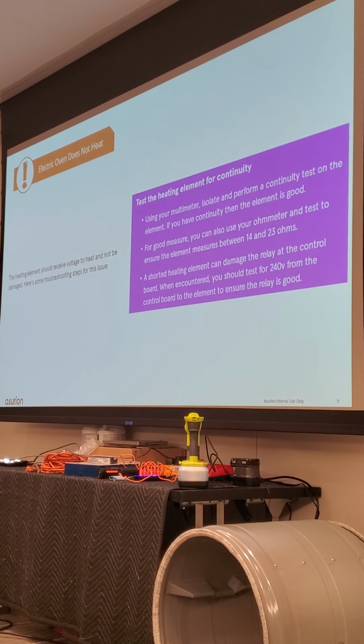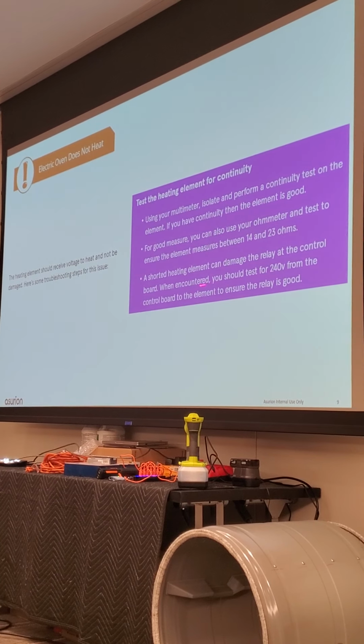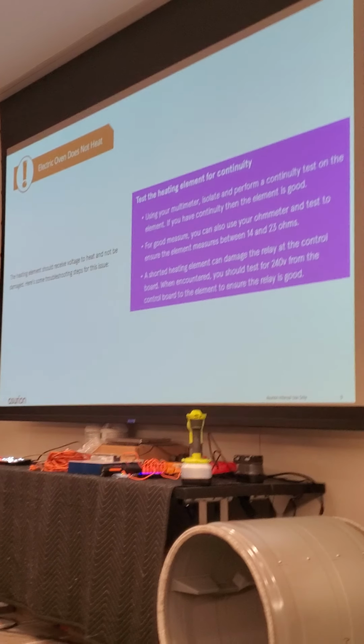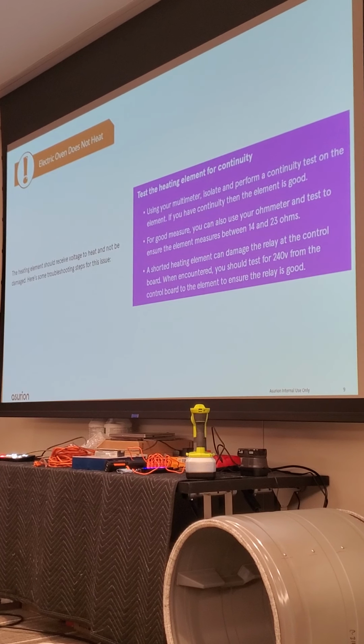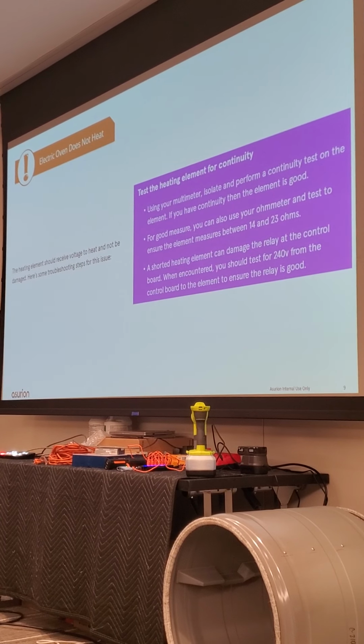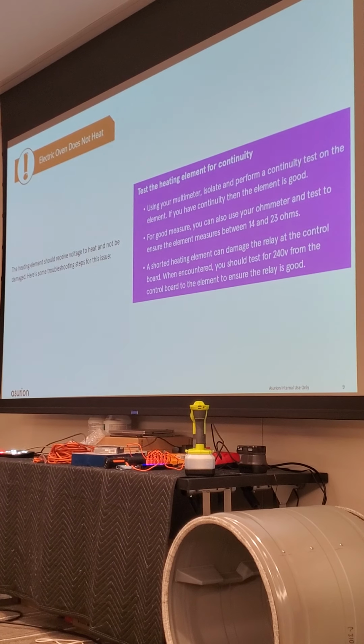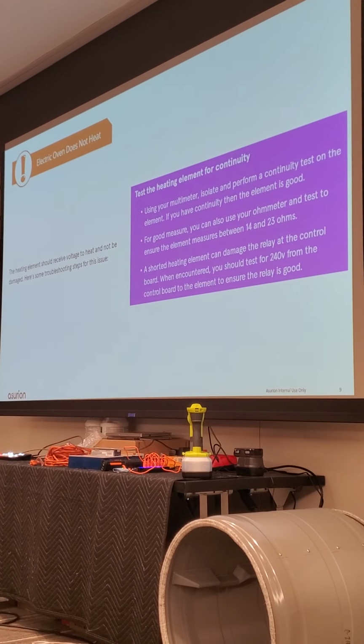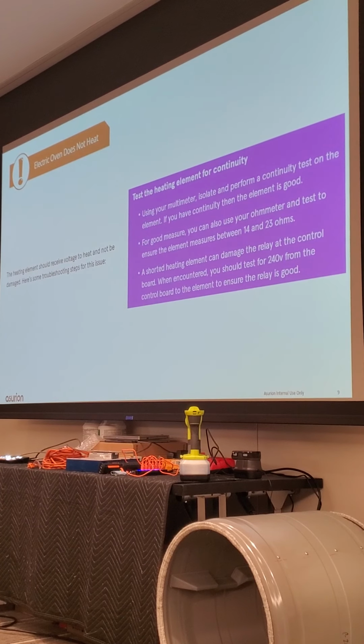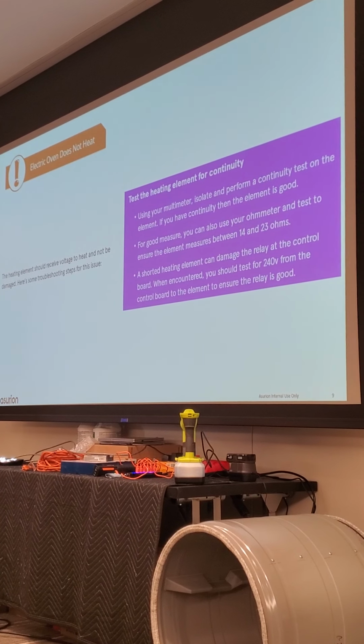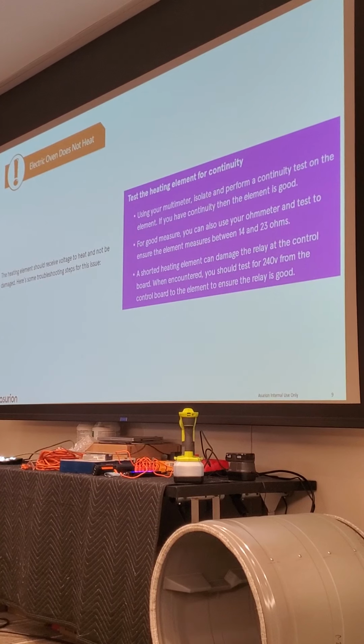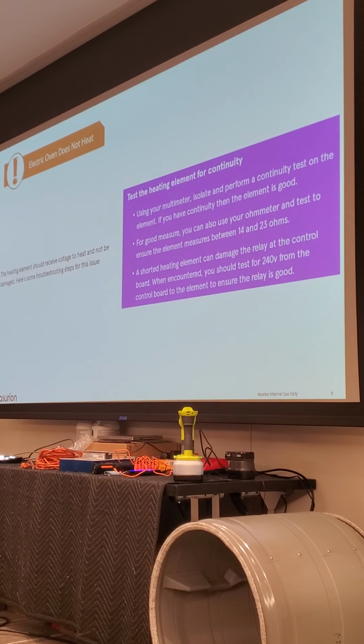Because it is a straight path - it starts on one end, comes around and goes back out the other. There is no break in that whatsoever. So if you have ohms, you have continuity. I always tell you to check the ohms so you can put down a reading, and guarantee you that continuity does not give you the correct ohms. So ohms will actually be a better test, okay?